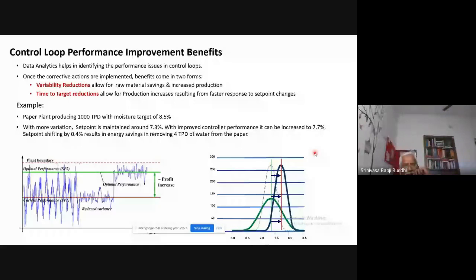Like that, they take all the corrective actions so that the performance improves. When we implement such a continuous performance monitoring, tuning, and improvement system in the plant, you will get improvements in the plant from two reasons. One is the variability reduction. Once you tune the loops and make them work properly, the variation in the process variable will reduce. Once you have less variation in the process variable, that will help you to save raw materials and also increase the production. And the time to target reduction.